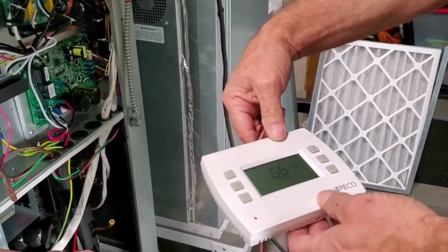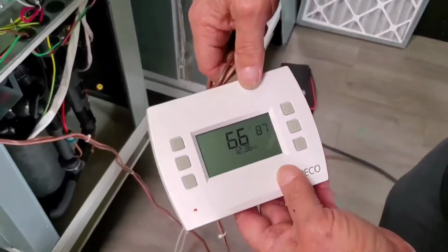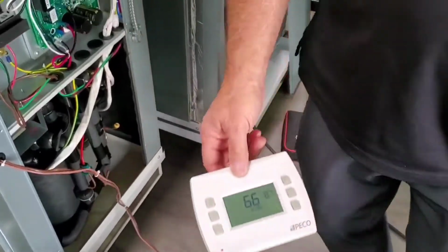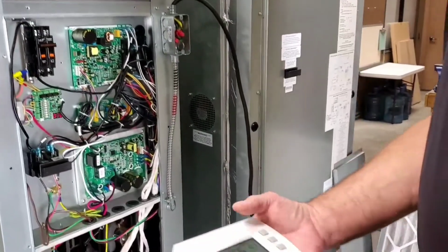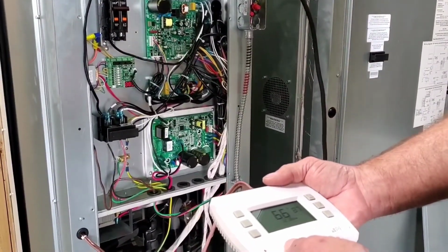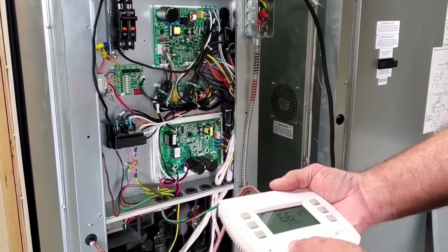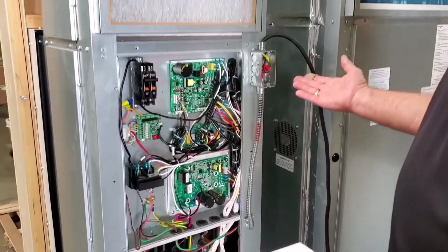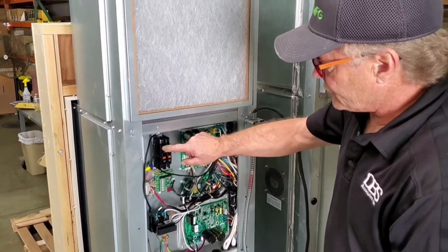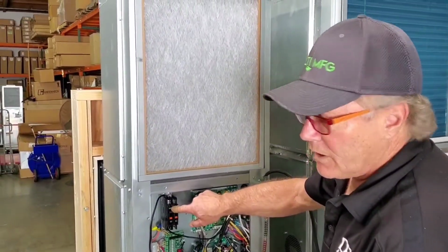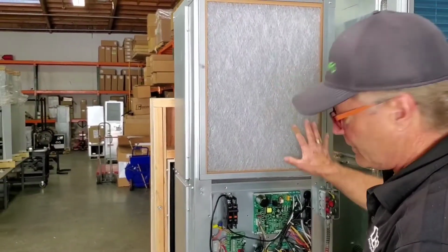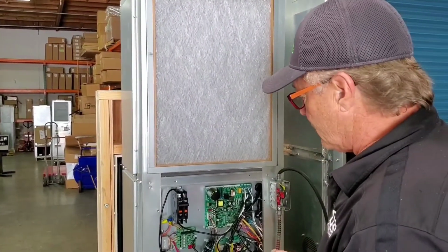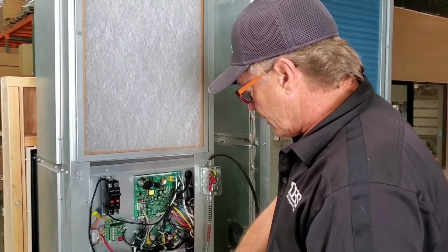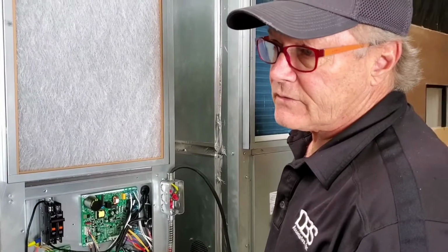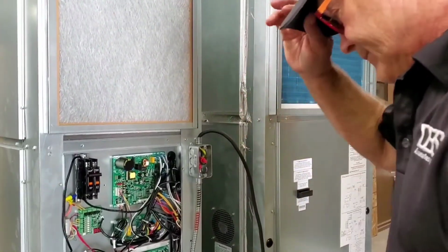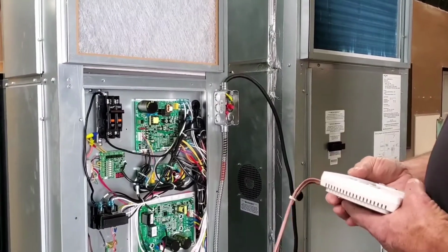Right now we are calling for heat. 87 degrees at 66 room temperature. Okay, the fan will ramp up, and for 120 seconds, the strip heat will be energized. This is in the heating mode to preheat the coil and the system before it brings on the compressor. So for 120 seconds, you'll have the heat strips operating, no compressor operation, and then at the end of the 120 seconds, it'll kick into the compressor, and the compressor will bring it all on. So we'll just wait for that.